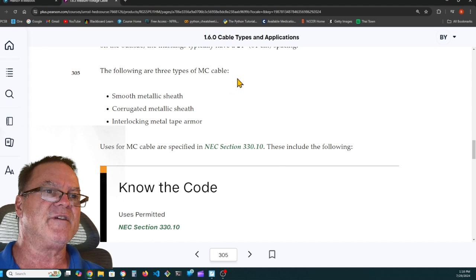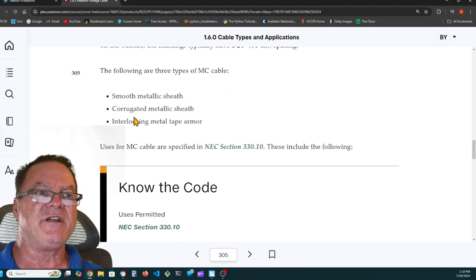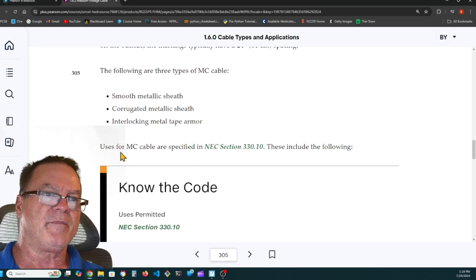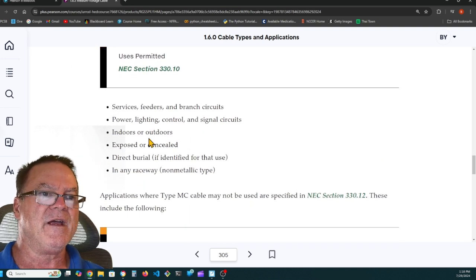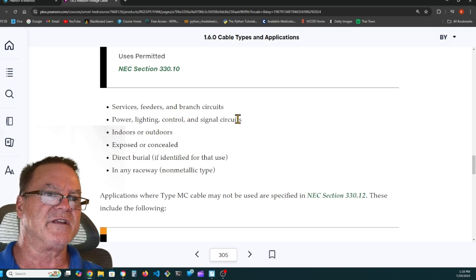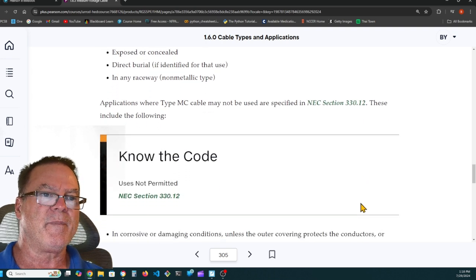Following are three types of MC cables: smooth metallic sheath, corrugated metallic sheath, and interlocking metal tape armor. Uses for MC cable are specified in NEC section 330.10. These include the following: services, feeders, branch circuits, power, lighting control, and signaling circuits, indoors and outdoors, exposed or concealed, direct buried if identified for the use, and in any raceway non-metallic type.